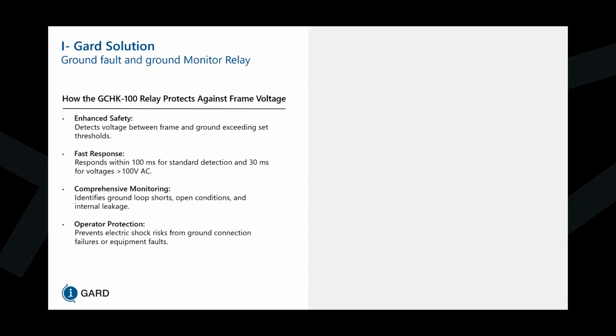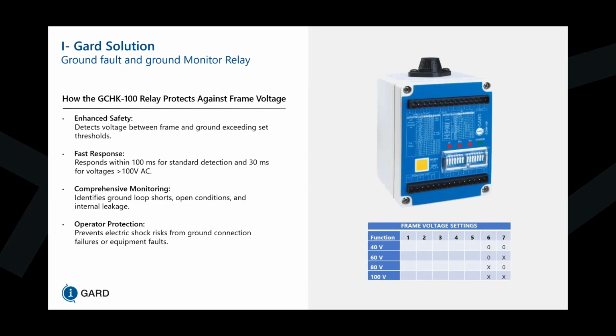Now, I-Gard's solution is a combination of a ground fault ground check relay or ground monitor relay, and the GCHK 100 protects against frame voltage as well. So it has 3 functions. It can pick up ground fault, it can pick up open circuit and short circuits along the trailing cable's ground connection, and it can also pick up frame voltage between 40 to 100 volts. So the response time is within 100 milliseconds for standard detection and 30 milliseconds for voltages greater than 100 volts AC. As I mentioned, it identifies ground loop short and open conditions and internal leakages with respect to ground fault.